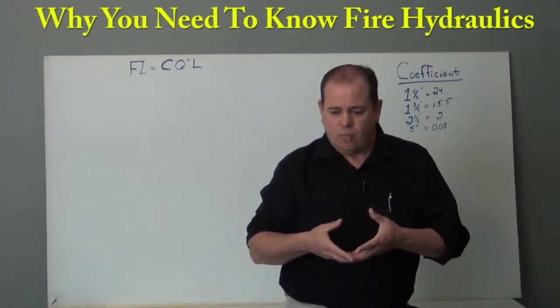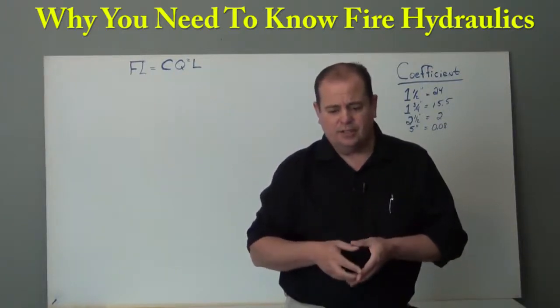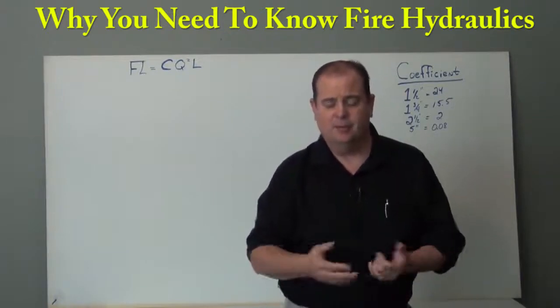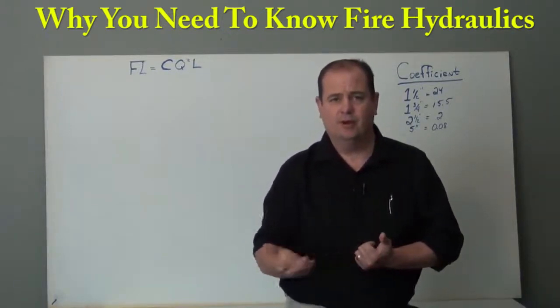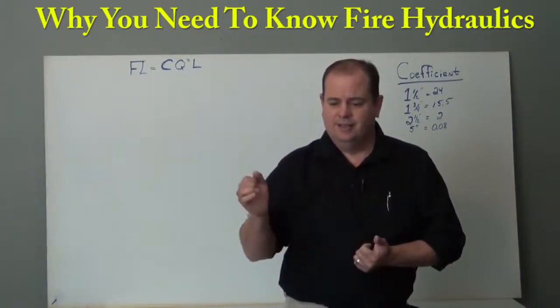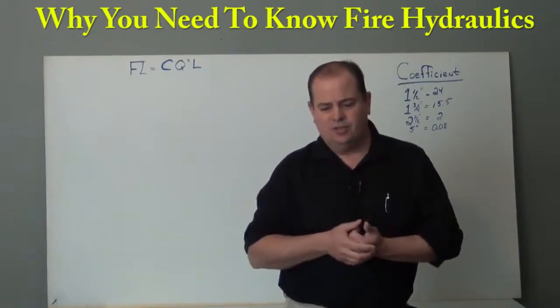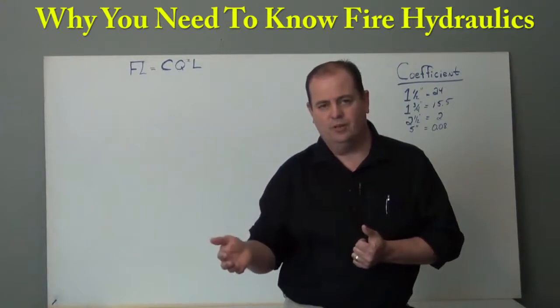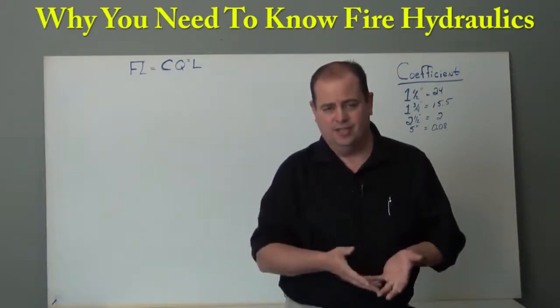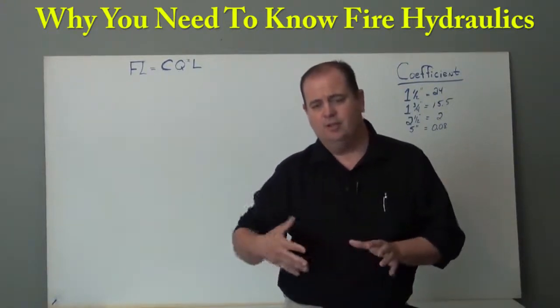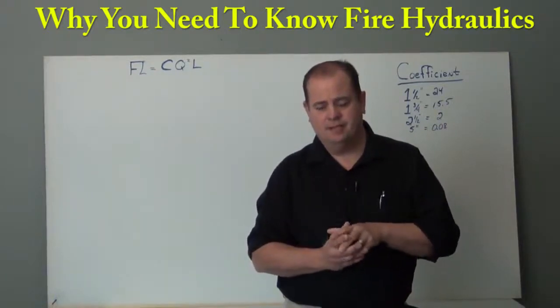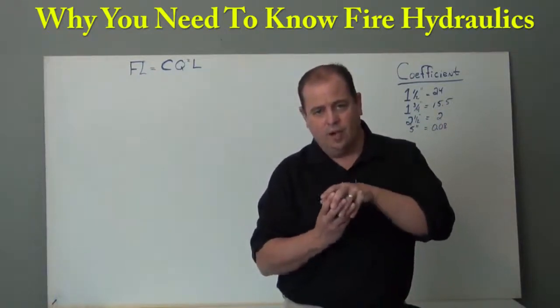But let's say you're speccing a truck and you're thinking about adding a task force tip. Say it flows 185 gallons per minute, for example. I'm just using that because that's what some of our nozzles are rated at. If you do the equations and you figure out that if I put more than 200 feet of hose on that, using say 1 3/4 inch, anything beyond that I'm pushing the maximum capacity of what that hose can handle on pressure.